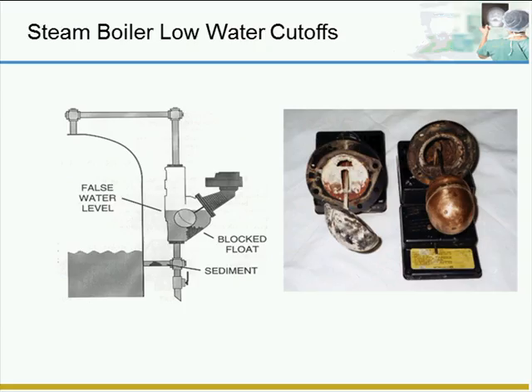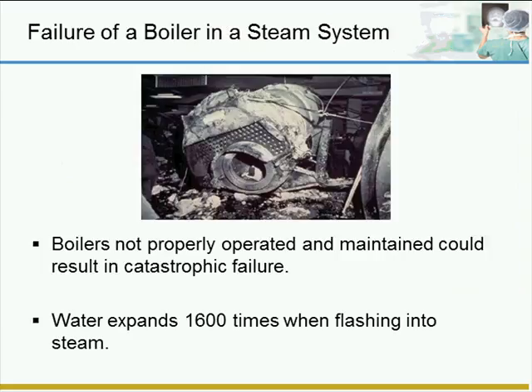When the low water cutoff drops below that given level, it should kick off the fuel source, being the burner, and the boiler should shut down, not allowing combustion and the level to keep going lower. This is what can happen when a boiler doesn't properly shut down.